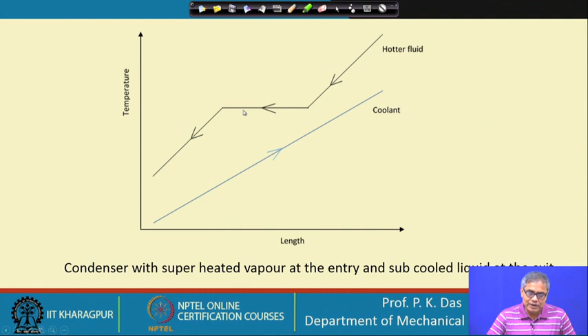So, in most of the practical cases we will get a heat exchanger like this. Let us consider the condenser of a refrigeration unit. In a refrigeration unit, after the compressor hot vapor comes out, and that will be in a superheated state, and then in the condenser it condenses, either partially or fully, but obviously it will enter the condenser in a superheated state. So, the curve will be something like this, either it can go to this range or it can come out of the condenser like this. Subcooling may or may not be there, but obviously there will be a superheated vapor which is to be cooled first and then condensed.